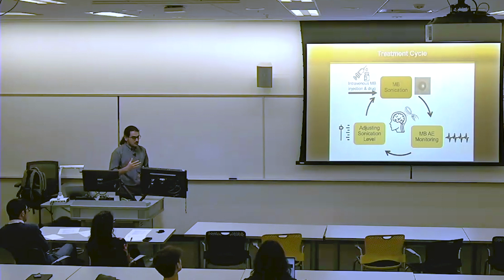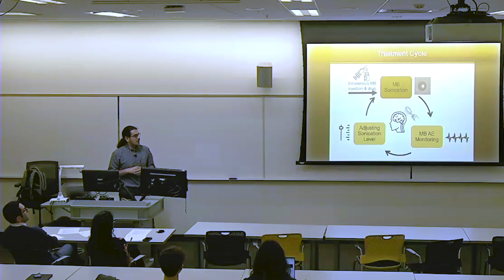This is the treatment cycle. To understand microbubbles and the treatment better, initially the microbubbles and drug are injected into the bloodstream, then external sonication is started. When we start sonication, we also start listening to capture those unique harmonics. Capturing those harmonics allows us to adjust the sonication level so we can keep the microbubbles in stable cavitation, which effectively opens the blood-brain barrier.